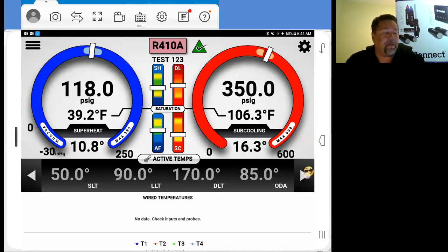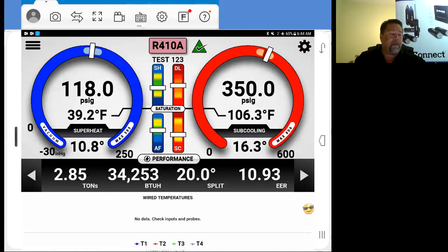On the bottom here, you see the arrows. This will scroll back and forth between screens as far as active temps. I go over to my left side and just tap over here. With all this information, we're calculating. There's our tonnage that we're producing. There's our BTUs, 34,253 BTUs. Our temperature split between our supply and return is 20 degrees. And with the electrical input that we just put in here, we've got a 10.93 EER. Pretty amazing. So I'm going to keep going on this left side arrow.